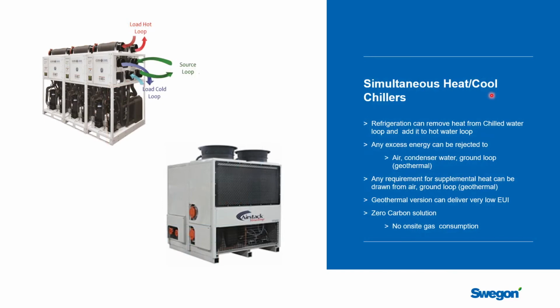So let's talk a little bit about driving to a carbon neutral, very high performance chill beam system. A chill beam system is going to make your short list of highly efficient HVAC systems for a lot of building types. So if you're driving to a very high energy performance building, chill beams are going to be an attractive solution. If you want to drive to a carbon neutral building, one that doesn't require on-site burning of natural gas, you can do that with a chill beam system by looking at simultaneous heat-cool chillers, sometimes called heat recovery chillers. So let me just show you a couple of types that are in the marketplace.